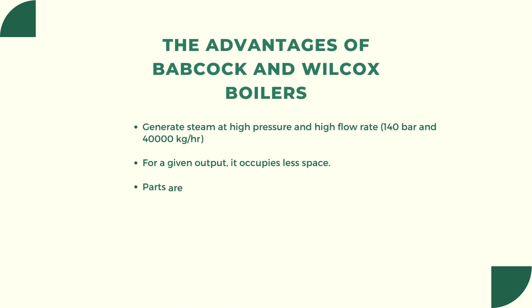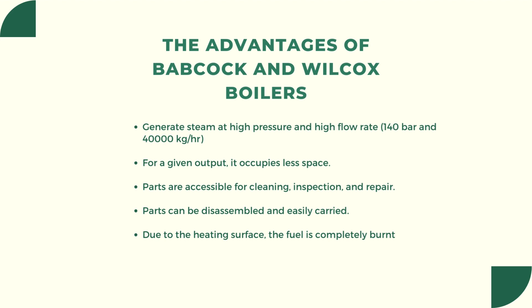Now, the advantages of Babcock and Wilcox boilers are: steam generation at high pressure and high flow rate. For a given output, it occupies less space. Parts are accessible for cleaning, inspection and repairing. Parts can be disassembled and easily carried. Due to the heating surfaces, the fuel is completely burned.